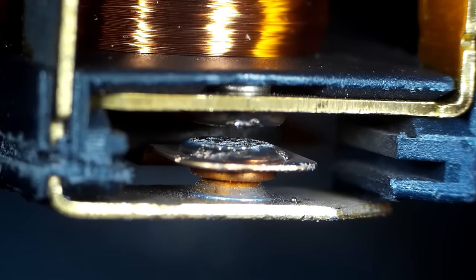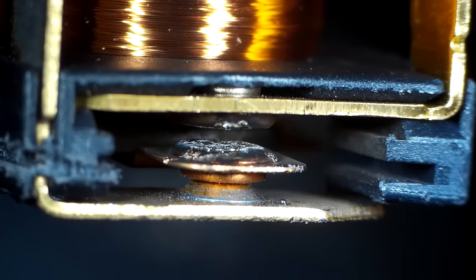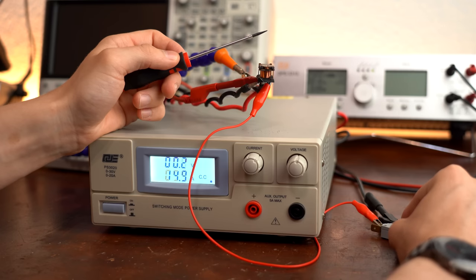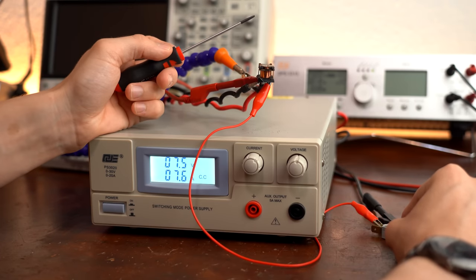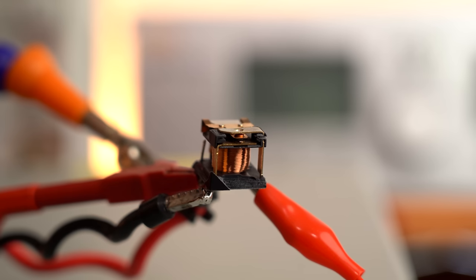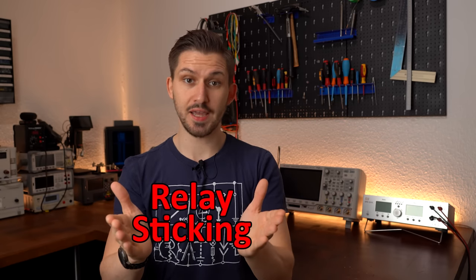Now I think everyone can guess that those sparks are not good for the relay. They not only destroy the contact material but sooner or later they will weld them together so that the contacts cannot open anymore when unpowering the relay. And only a well placed smack can separate them once again. This occurrence is called relay sticking.